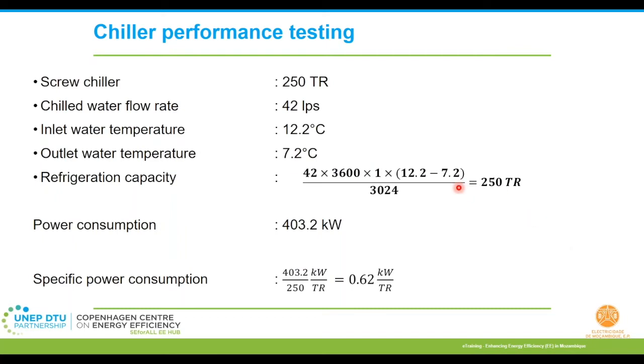It basically gives you how to evaluate an example for the cooling load, and then also how to evaluate the specific consumption here. As a thumb rule, the lower the specific power consumption, the more efficient. So you can compare these operating values with your design rated values and see what is the deviation. And also, I have given you in the previous slides how to convert it into, let's say, COP or energy efficiency ratio. So that can also be converted and compared.